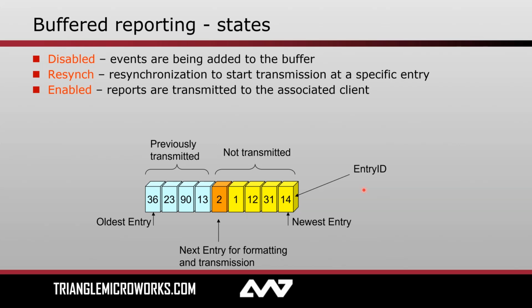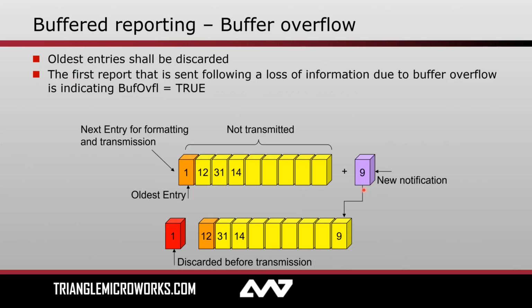And then finally enabled. So in this state, the report control block is fully enabled, the buffer has been passed up to the client, and just as new changes come in, those are processed and sent up to the client. So of course, with any buffer, buffers cannot be infinite size. So there is an opportunity for a buffer overflow. The size of the specific buffer will depend on the manufacturer and the implementation, but ultimately they all are limited in their size and scope. So in this case, where we have a buffer overflow, a lot of data changes have occurred while no client was connected. Eventually the overflow occurs and the oldest entry is going to be discarded, tossed out of the buffer.